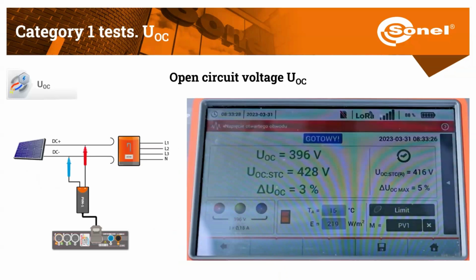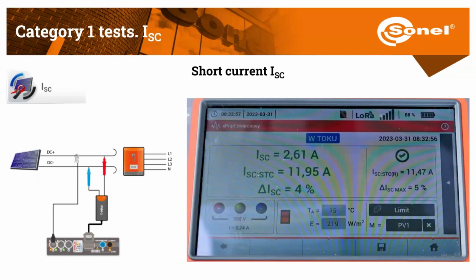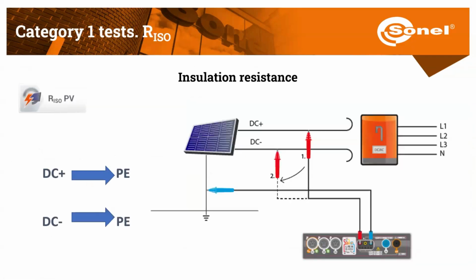Next test is to measure the open circuit voltage. Some meters may need an additional accessory to perform this test. For the next test, which is measuring the short circuit current, we may also need additional accessories in some cases. Only under specific conditions can we check the short circuit current. By knowing the temperature and radiation levels, we can convert the measured current to standard condition. As you see here, we have the value of measured current, and here we have the value of current in standard condition. This is recalculated by the method.